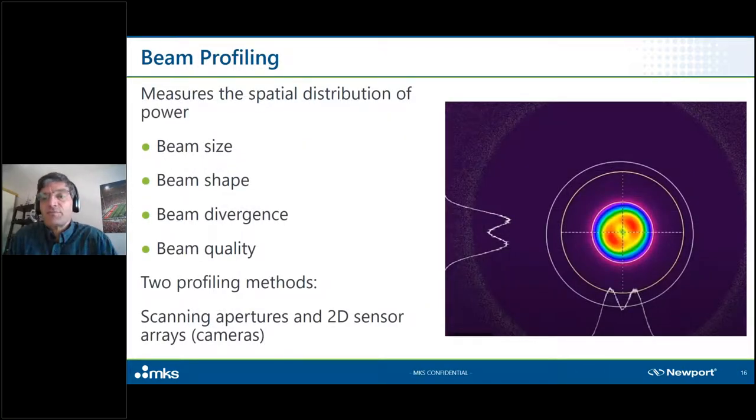So now I'm going to turn to beam profiling, and maybe I should just review what beam profiling is. We're looking at the spatial distribution of power. So we're looking at the size of the beam, its shape, its divergence, its quality. Those are the main things that people are trying to extract from a laser when they measure the profile.